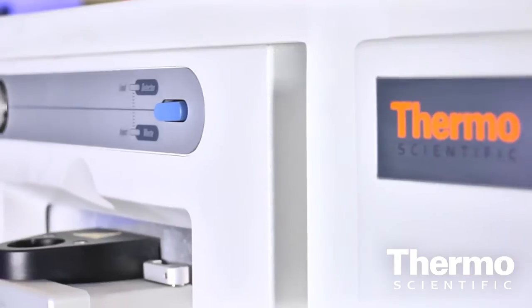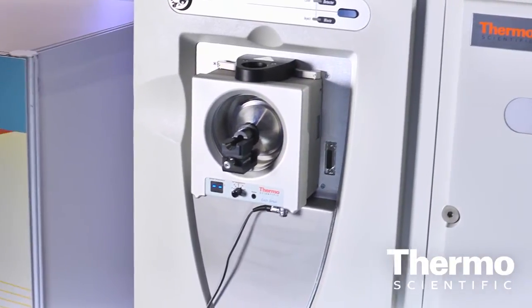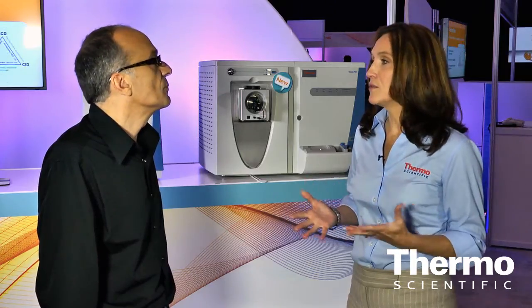TRAP-HCD is something like triple quadrupole fragmentation, which accesses a lot of lower mass-to-charge products, enabling improved structural elucidation capabilities. The Velos Pro has been used for a wide variety of applications, including biomarker discovery and comparative proteomics. You can also listen to a really nice set of applications described by Julian Sava in a companion piece, where he discusses glycoproteomics as well as glycomics, all done on the Velos Pro with ETD.